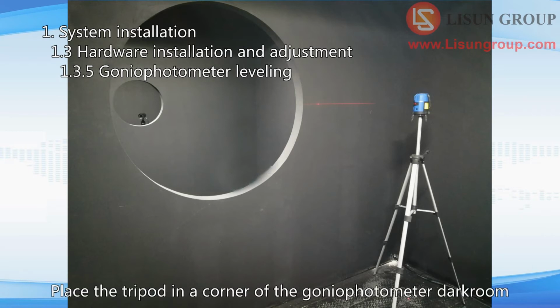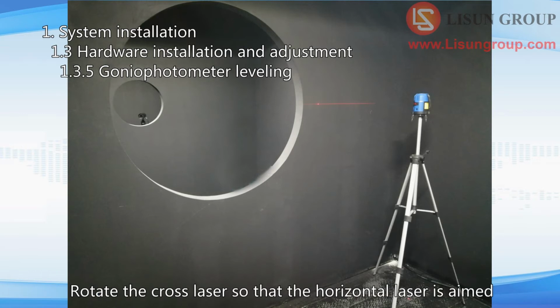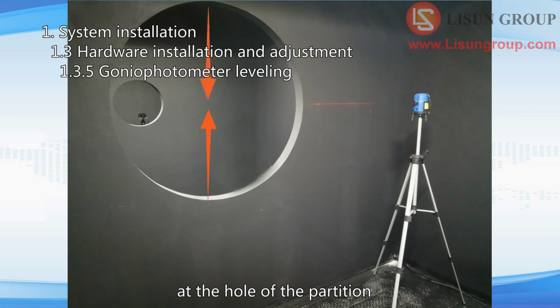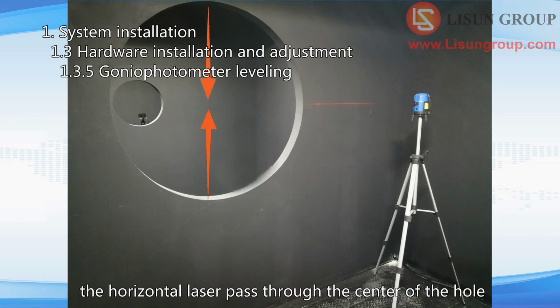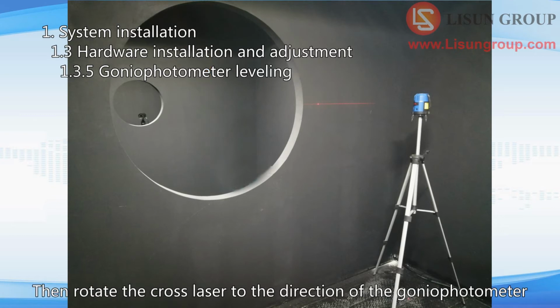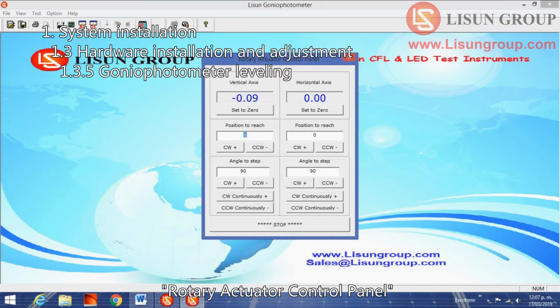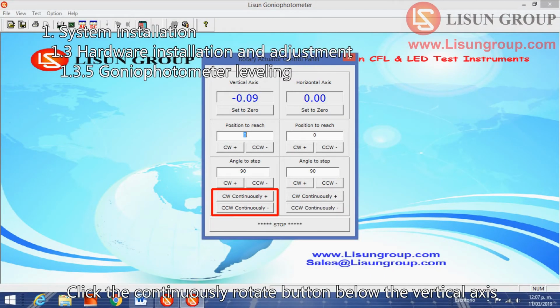Place the tripod in a corner of the goniophotometer darkroom. Rotate the cross laser so that the horizontal laser is aimed at the hole of the partition. Adjust the height of the cross laser so that the horizontal laser passes through the center of the hole. Then rotate the cross laser to the direction of the goniophotometer. On the rotary actuator control panel, click the continuously rotate button below the vertical axis.